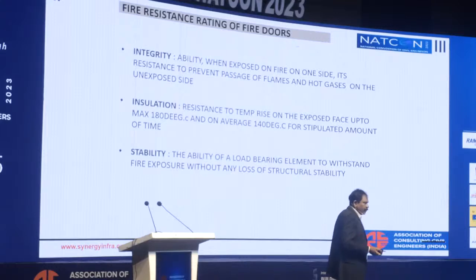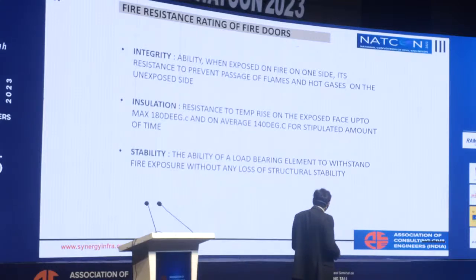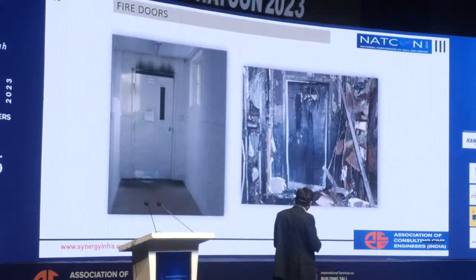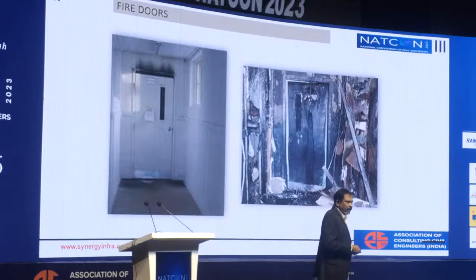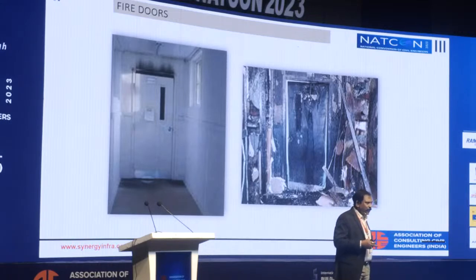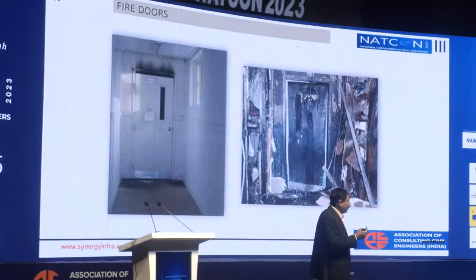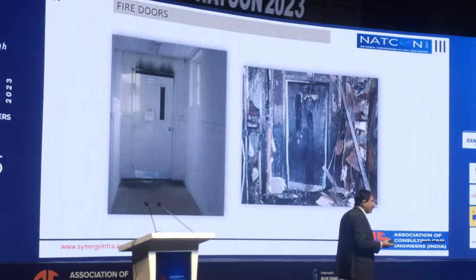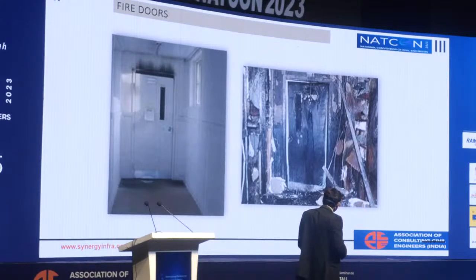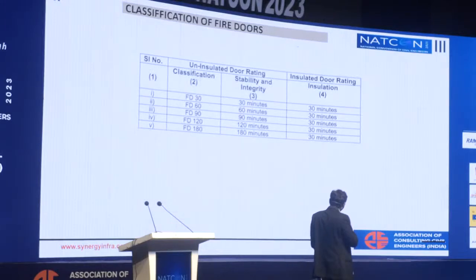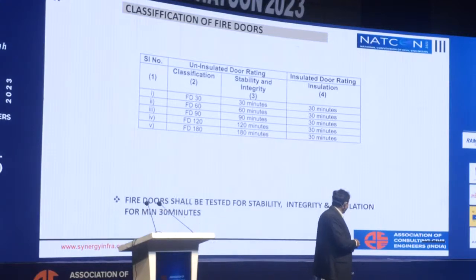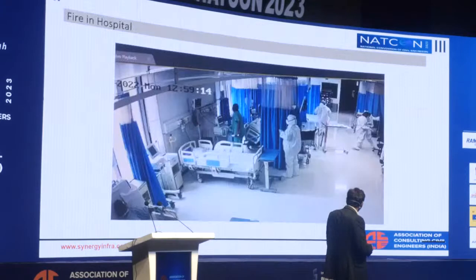All three could be different or the same, but in most of our cases we generally look only at integrity and insulation. Once there is a fire, the entire door assembly has to remain intact even after the fire. Otherwise, we see photographs where doors have openings filled with other materials, or the door windows are not properly sealed, or a frame is made on site and an untested fire door is fitted. It has to go in as a complete assembly and be tested as such. So you have uninsulated doors, insulated doors, FD 120 or 180, which need to be specified to take care of all three things.